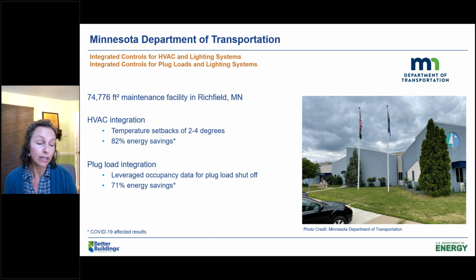In addition to the LED retrofit, the project included a networked lighting control system that integrated with the HVAC controls via BACnet with temperature setbacks of just 2 to 4 degrees. They achieved 82% energy savings, and by leveraging that same occupancy sensor data for their plug loads, they managed to turn those off for a 71% reduction in energy.